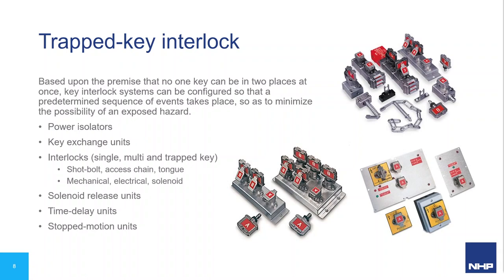Exchange units for trapped key switches link together other devices in the ProSafe range for more complex operating sequences — for example, one key in from an isolator releases five separate keys to open multiple guards, and all guards must be locked with keys returned before the isolator can be turned back on. Rotary interlock switches are used to isolate machinery for safe access and can also be used as teach boxes for robot cells. Once power is turned off the key can be withdrawn and used in the next sequence, such as unlocking an access hatch or entering a key exchange system. The switch can be panel-mounted or supplied pre-mounted in an enclosure.